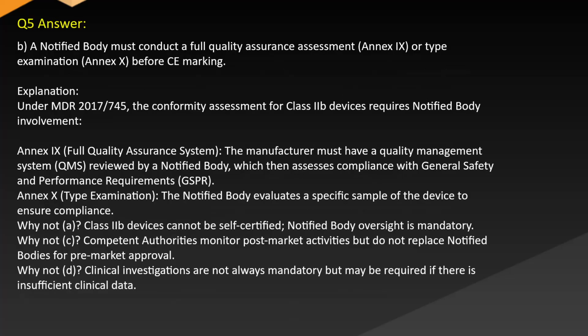Answer: B. A notified body must conduct a full quality assurance assessment or a type examination, Annex X, before CE marking. Explanation: under MDR 2017/745, the conformity assessment for Class IIb devices requires notified body involvement. Full quality assurance system: the manufacturer must have a quality management system, QMS, reviewed by a notified body, which then assesses compliance with the general safety and performance requirements, GSPR. Type examination: the notified body evaluates a specific sample of the device to ensure compliance.